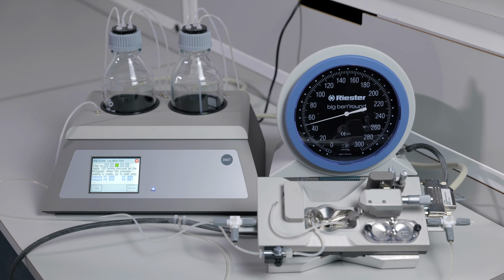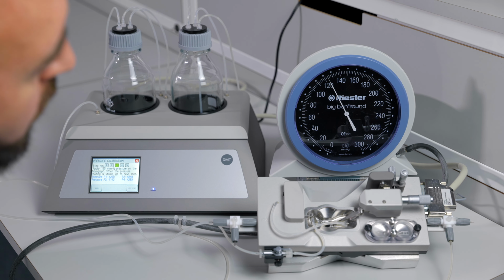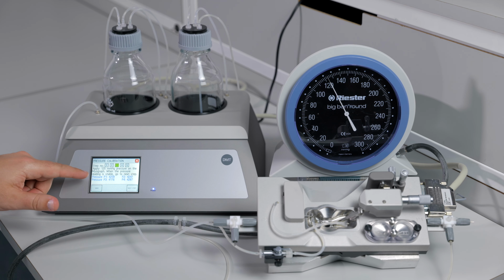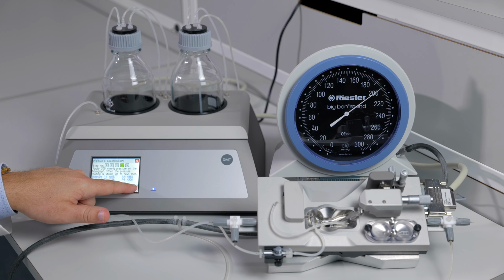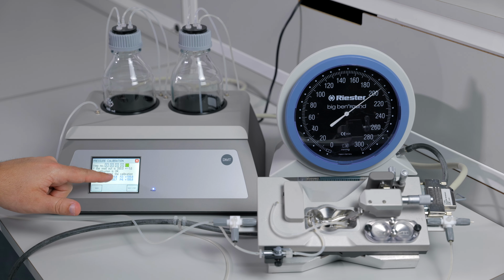We should now go to 125 millimeters of mercury of pressure. Again, all of the numbers have gone up a similar increase. Press Next Step. The last step is 200 millimeters of mercury. Again, they have all gone up. We can press Next Step, and all the numbers should be right around 200. Press OK, and pressure will internally release. This will complete the pressure calibration.